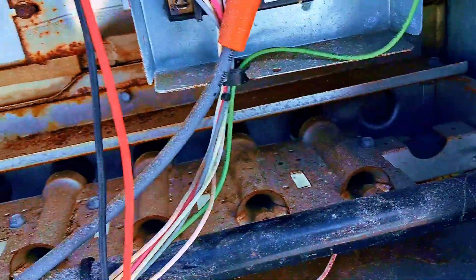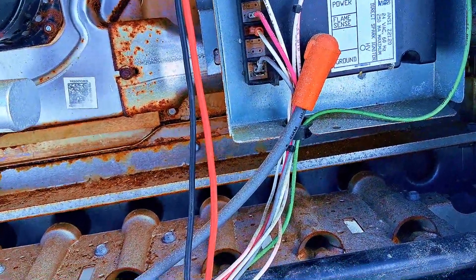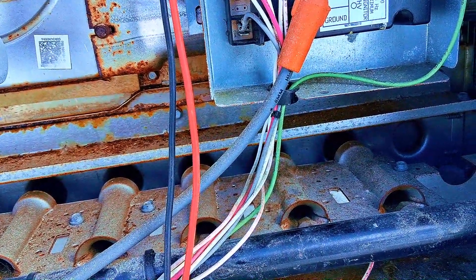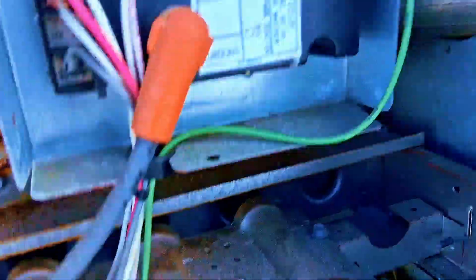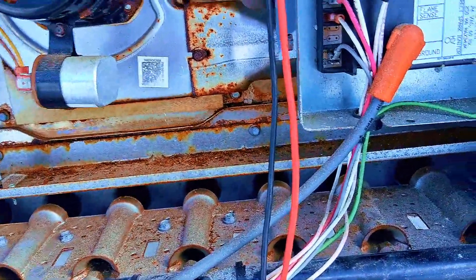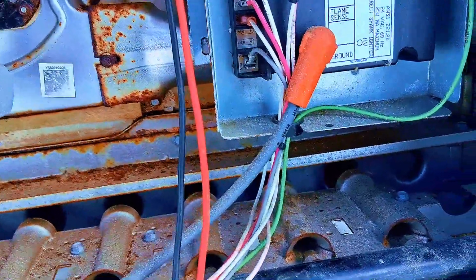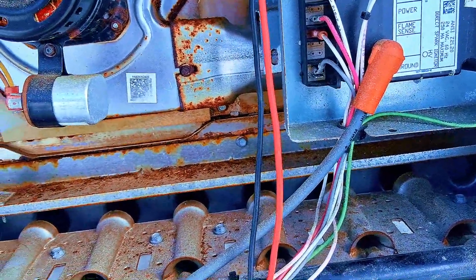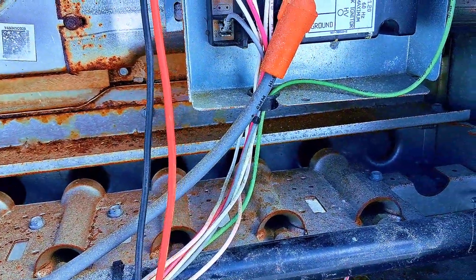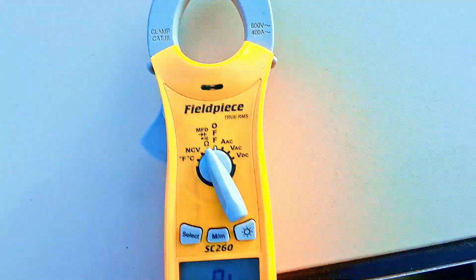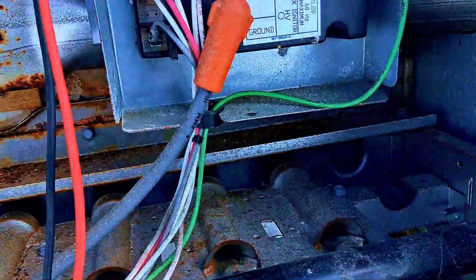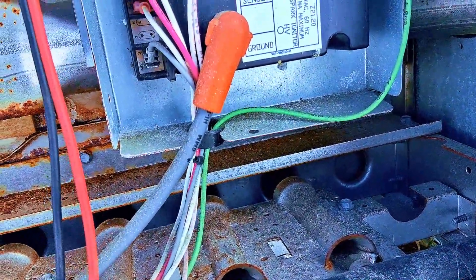What I think I have is some kind of flame rectification issue right now, where the flame sensor is not sending the signal back to the board at the proper amps, or the board is not able to read that the flame was actually on, and it's turning the unit off. So right now I gotta go get my other meter that reads microamps, so I can test the amps coming off of this flame sensor down here. I just cleaned it, as you saw, but it didn't help anything.